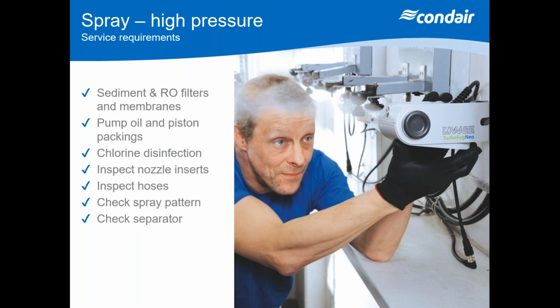So nozzle inserts and nozzles are definitely worth checking and changing out if they're not spraying correctly. And that will apply also to the spray pattern itself. Also, hoses need to be checked to make sure they're all okay, and it's worth changing those periodically as well to prevent any issues with biofilm building up inside there. And if you've got an induct system, it's always worth cleaning down the blade eliminator, because with these blade eliminators, they will have a certain amount of water being run across them. So it's always worth spraying them down with a disinfectant to make sure that's clean and the areas are clean.